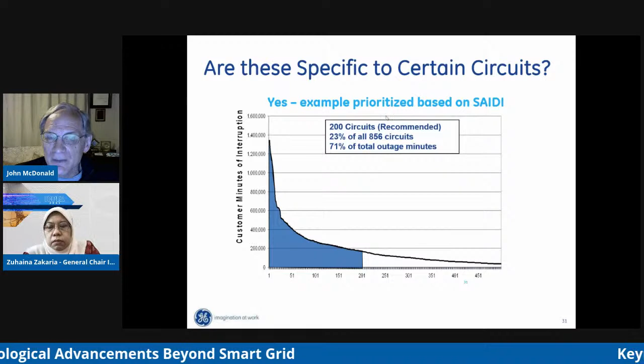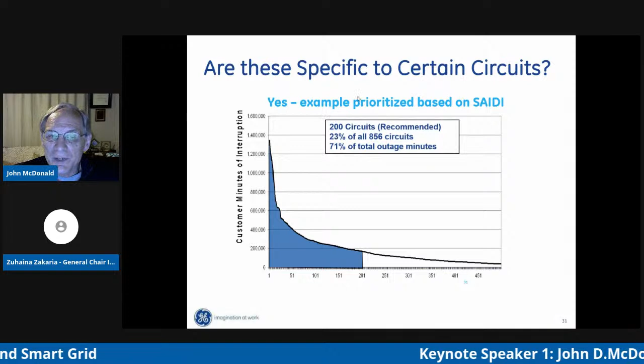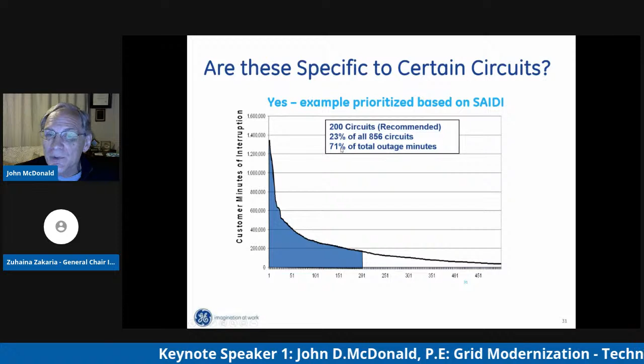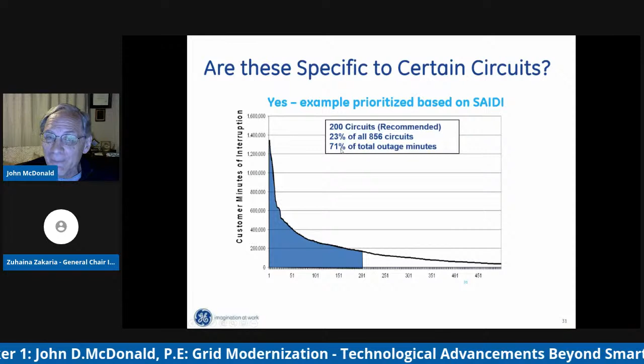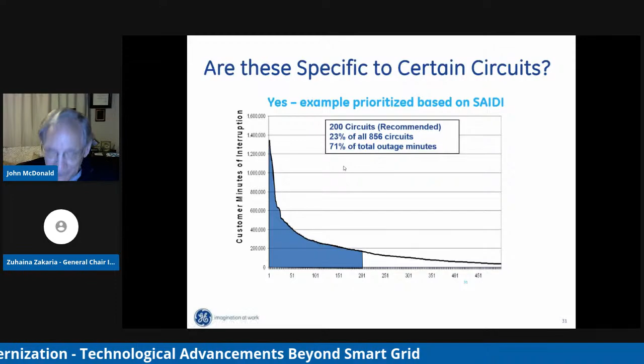At first, the thought is maybe we need to automate all 856 circuits. That'd be a tremendous expense, and do we really need to do that? Let's study this. In studying it, we found that only 23% of all the circuits contribute 71% of the total outage minutes. So only 200 circuits account for almost three-fourths of all the outage minutes. So we focus on those 200 circuits first, automate those, and we're addressing almost three-fourths of all the outage minutes. Much better use of funding, and getting the most return for the money we spend.